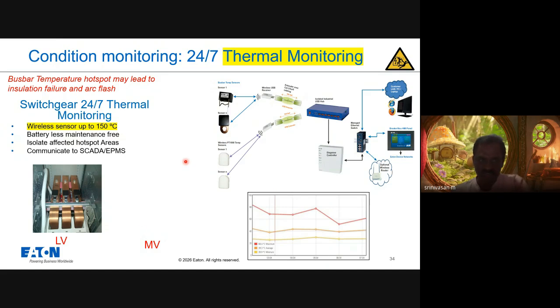This wireless thermal sensor system, as I said, we can clip anywhere on the bus bar. You could see the black color over here. It can measure the temperature up to 150 degrees Celsius. As I said earlier, it's battery free, so it's maintenance free, and it works 24/7. We can transmit the temperature data to a higher level like a BMS or SCADA system. Just one point I would like to highlight: only the first point of the signal going into the measurement is wireless. From this USB receiving port onwards, it is all wired, just for better clarity to you.